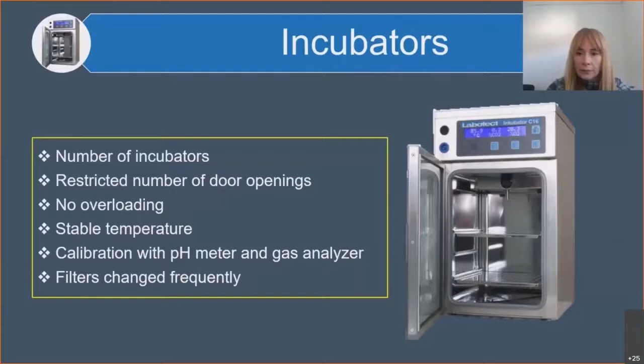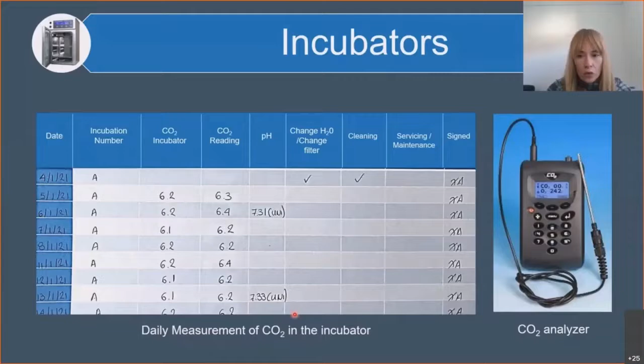So this is a type of quality control you can do in your lab to measure daily the CO2 in the incubator. CO2 measurement is an indirect way of measuring the pH, but it's very quick, so we can do it even daily. However, we need to do once in a while also the pH measurement, that is direct measurement, but it's more time consuming.